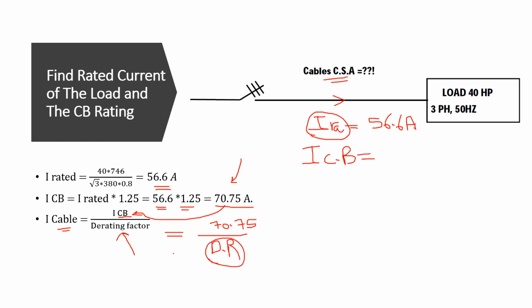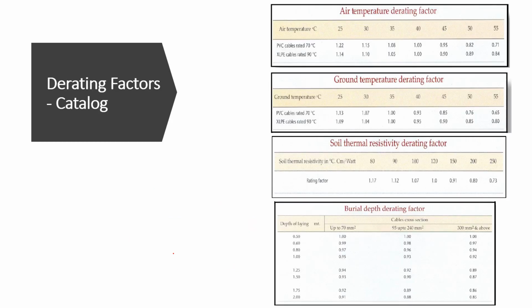We can get this factor from the catalog. Inside the catalog, for example for XLPE cables, you will find different tables having derating factors. You can see an air temperature derating factor, a ground temperature derating factor, a soil thermal resistivity derating factor, and a depth derating factor. All of these factors we need when we design our cable, in addition to other factors such as grouping factors and so on. First we need to understand where our cable is installed.